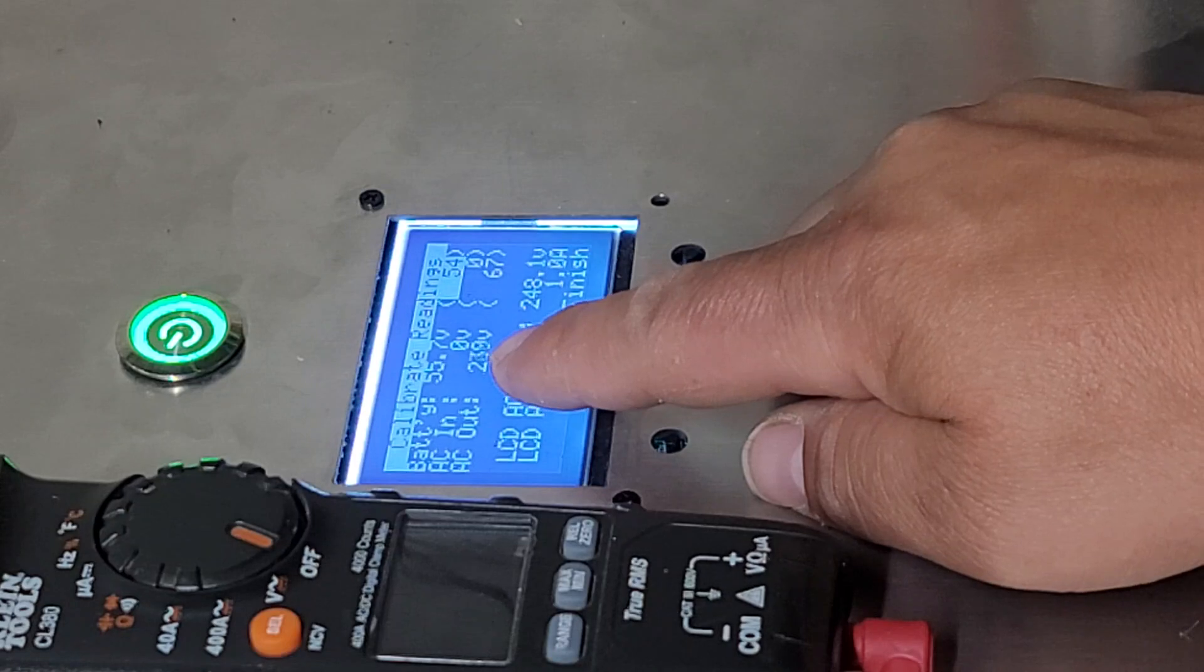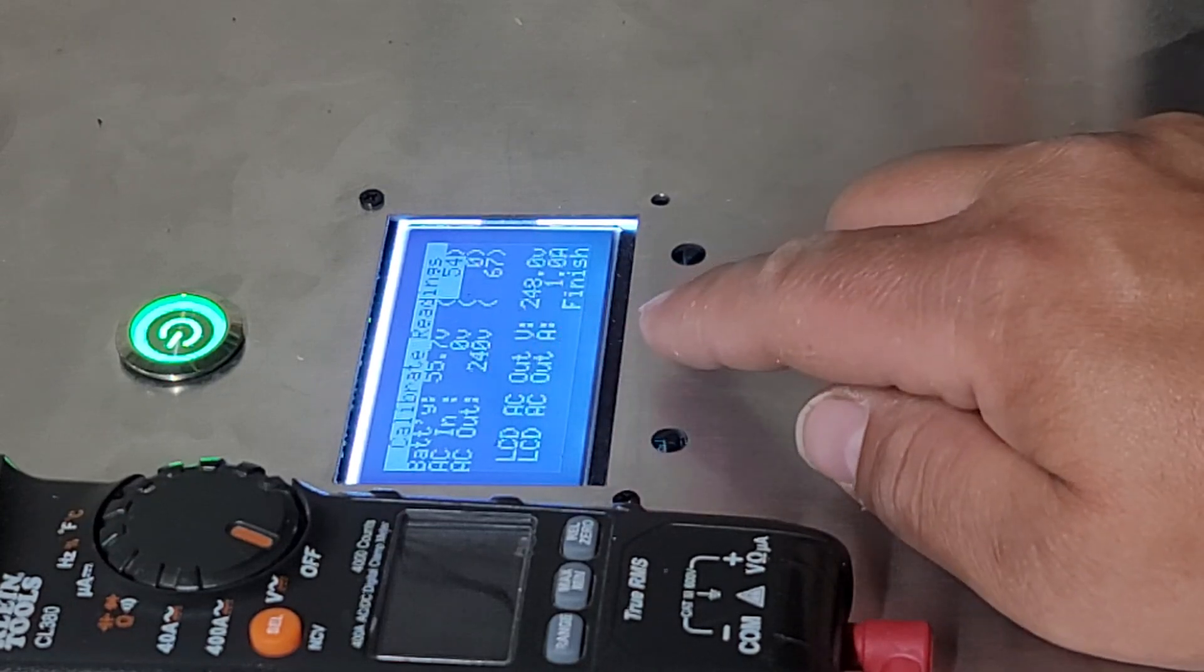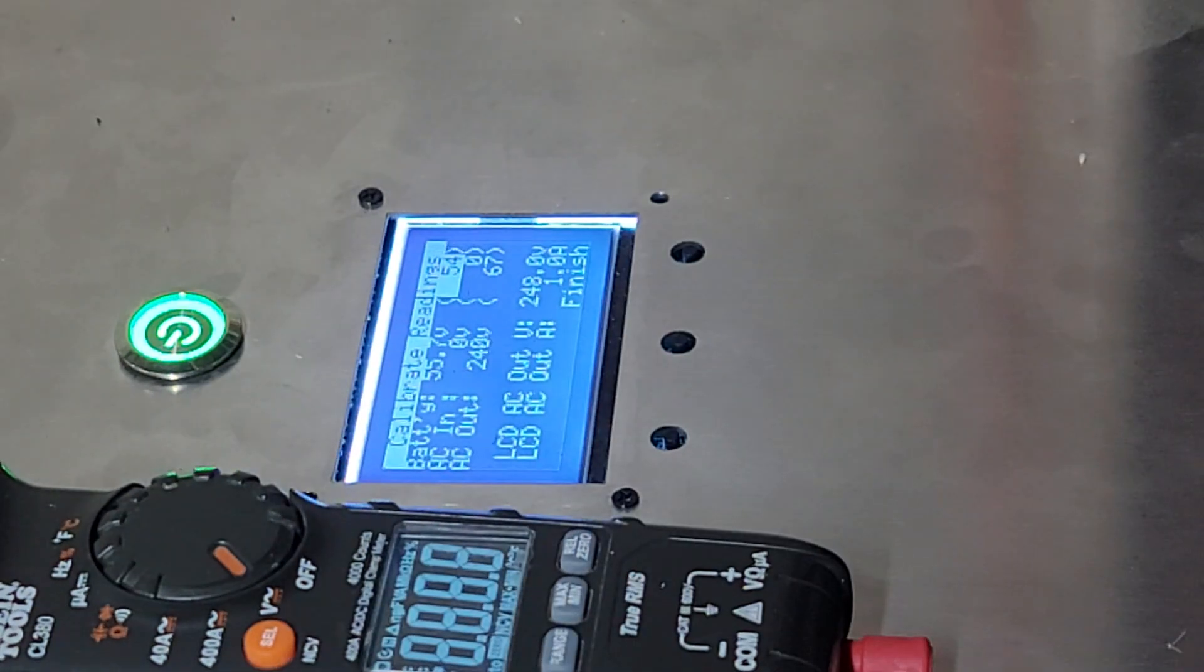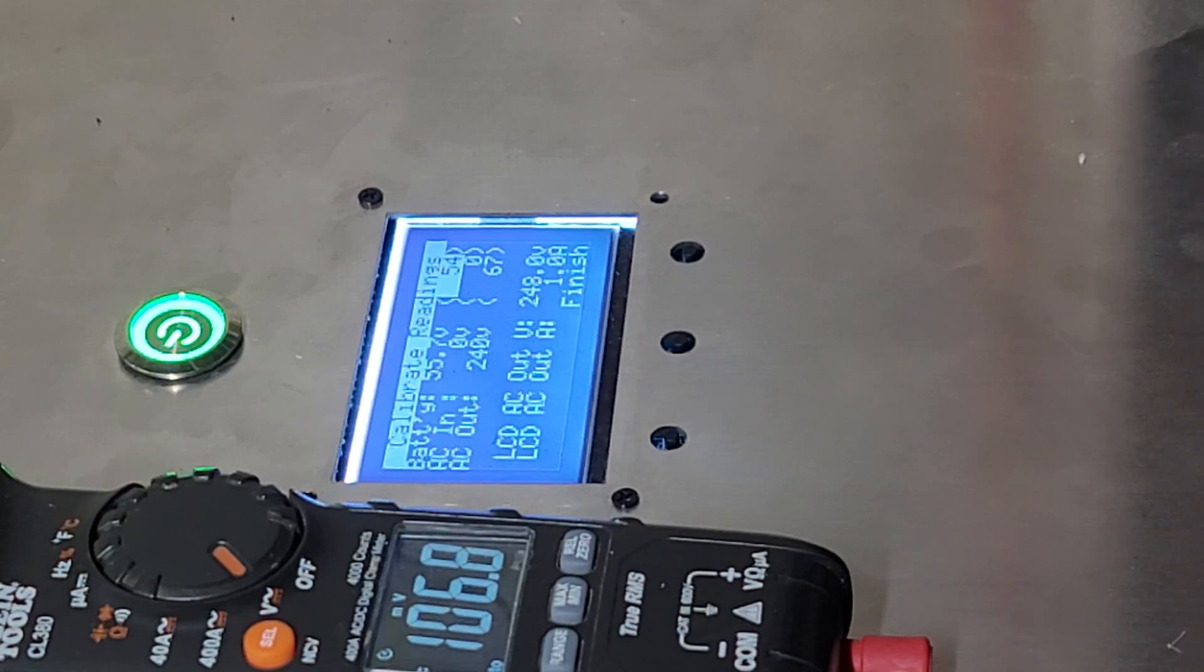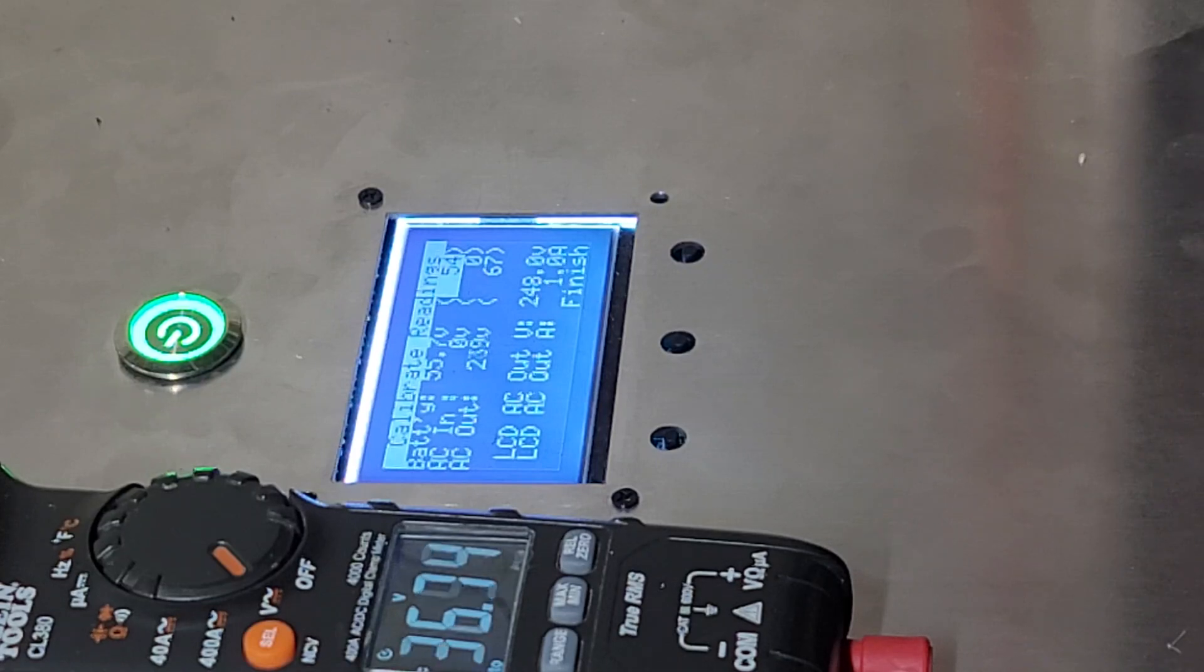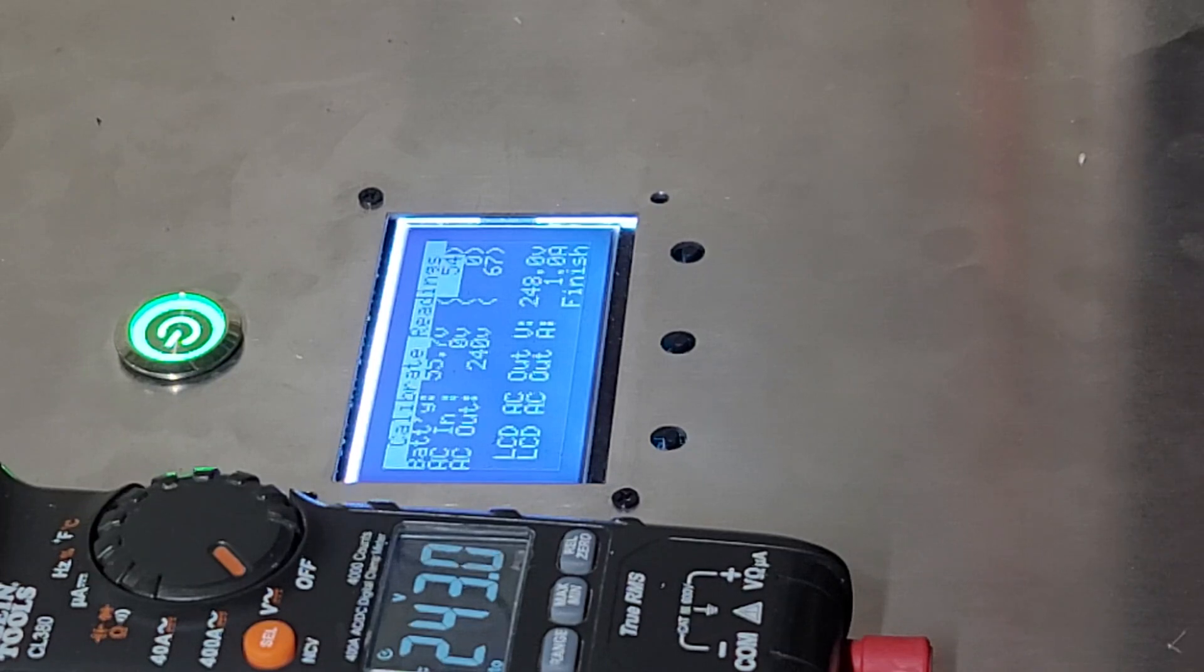Again, right now the CPU is pushing for 240 volts. Do we have 240 volts? Well, let's find out. I can already tell you that I don't because I calibrate mine slightly higher. That's definitely not 115 volts or else the lights would dim. There we go. We're at 243 on the AC output voltage.